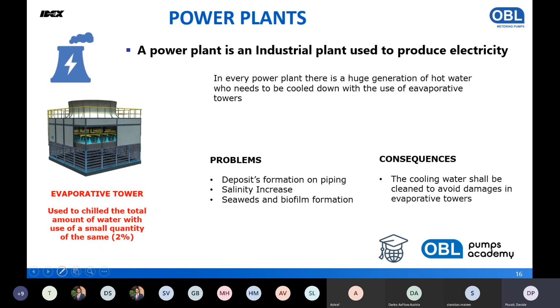The working of an evaporative tower is to chill the total amount of water using a technology that uses just a small quantity of it. If the water isn't totally clean, there will be a lot of deposit formation on piping - a problem of salinity increase due to evaporation, minerals, and formation of seaweeds and biofilms. The consequences can be terrible, and cooling water must be kept clean to avoid damage in evaporative towers. You can understand that the cost of these evaporative towers is very high.